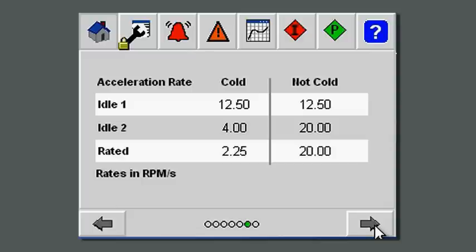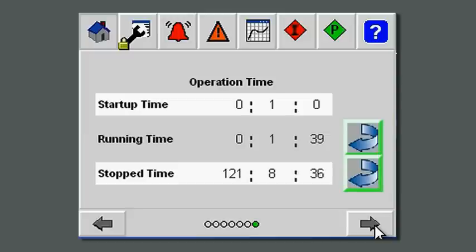As you get into a cold or not-cold startup, you can have different times that you spend in each of the idle zones. Operating time gives you an indication of how long the turbine has been running, how long it's spent in startup mode, and how long it's been shut down. This is useful information for determining when maintenance needs to be done on your turbine.